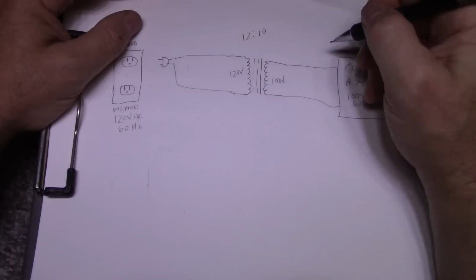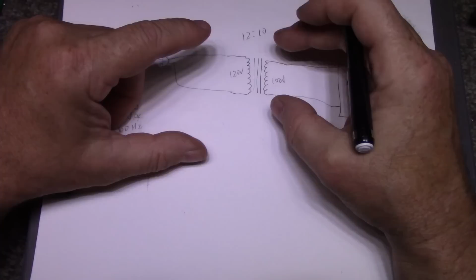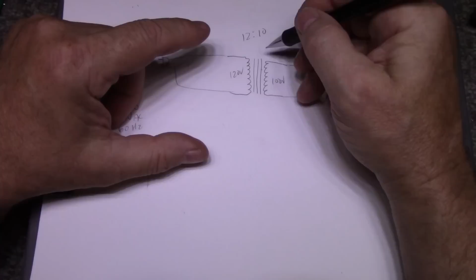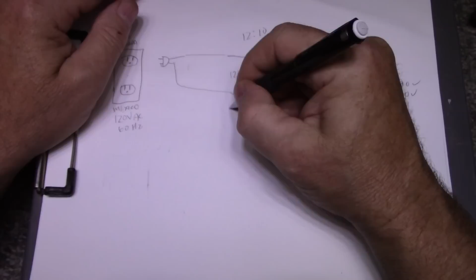Problem with this is power. Transformers that need to deliver the amount of power have to have a certain size, so you can't use a small transformer, because it will run out of steam when it gets to even a moderate load. And if you turn up the volume, you get a higher load, and the regulation is fairly poor, because you're going to have losses, including IR losses.